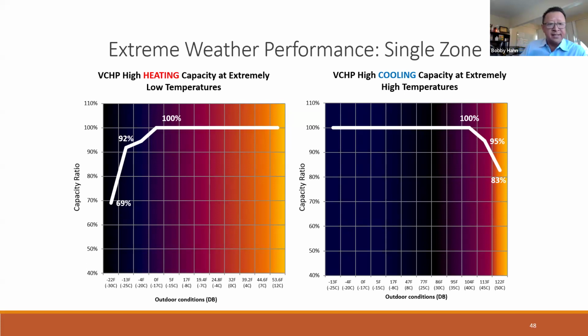As you can see, on the left-hand side is going to be heating. So we mentioned earlier, this is a new type of heat pump. It's an inverter-driven heat pump. These are variable capacity heat pumps. So in extreme weather, like on the left-hand side, if you look at 0 degrees, we're almost getting 100% capacity. What's different here is we injection flash the compressor with refrigerant so the compressor can run at extremely high rotation and extremely low temperatures and still get high performance.